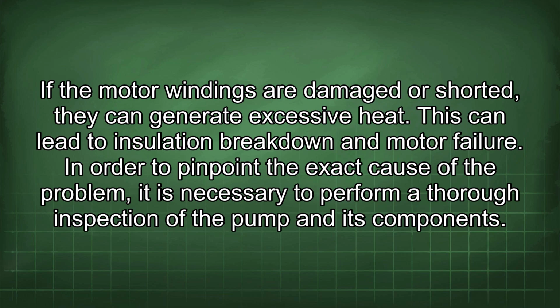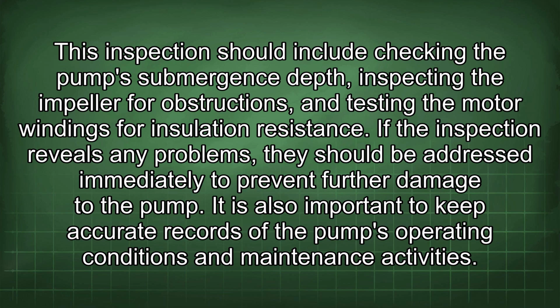In order to pinpoint the exact cause of the problem, it is necessary to perform a thorough inspection of the pump and its components. This inspection should include checking the pump's submergence depth, inspecting the impeller for obstructions, and testing the motor windings for insulation resistance. If the inspection reveals any problems, they should be addressed immediately to prevent further damage to the pump.